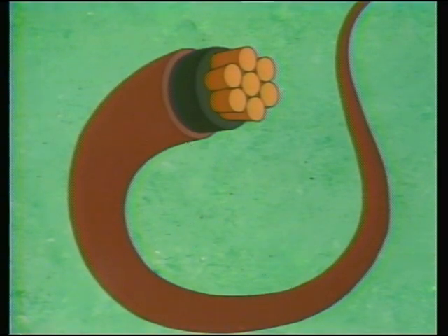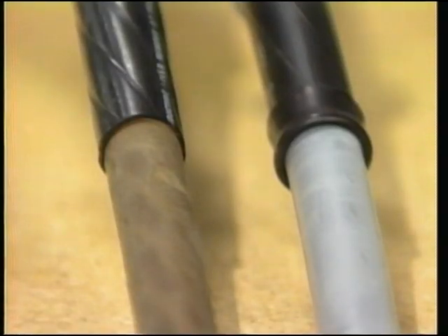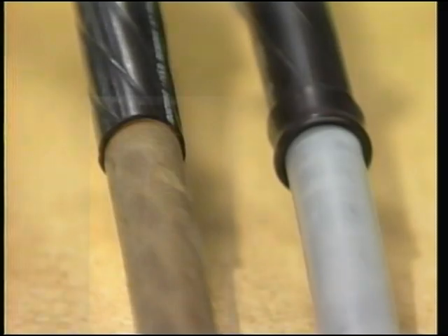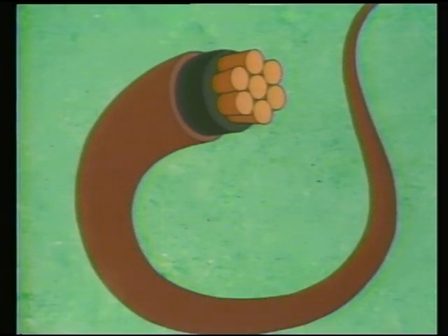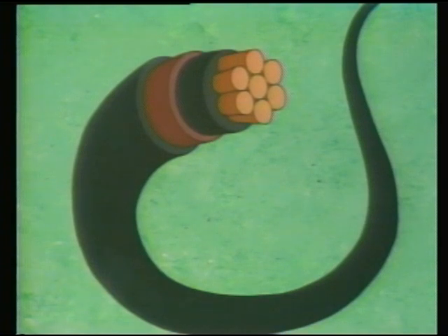It has a high insulating property that keeps the energized conductor isolated from ground or other conductors. Two common types of cable insulation used in primary URD applications are cross-linked polyethylene, commonly called XLP, and ethylene propylene rubber, commonly called EPR. Placed over the cable insulation is the insulation semiconductor shield.